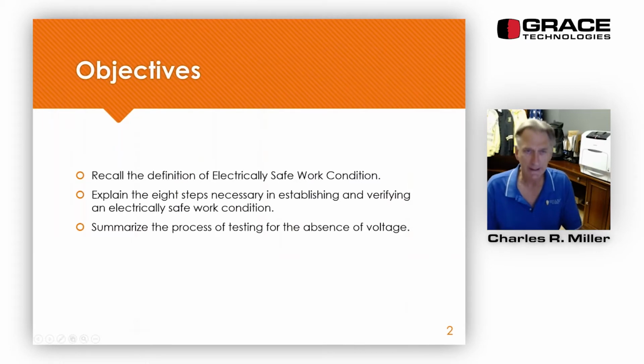All right, so our objectives are to recall the definition of electrically safe work condition, which in NFPA 70E there is a definition. We're going to talk about that. We're going to explain the 7 or 8 steps. There's really 8 steps, but step number 8 is typically for medium and high voltage. And then we're going to summarize the process of testing for the absence of voltage, which is a big part. It's only one step in the 8 steps, but it's a big part of those steps.